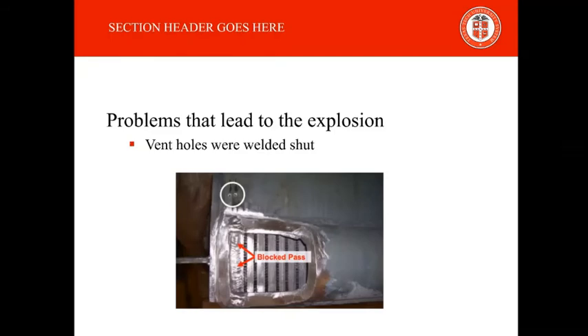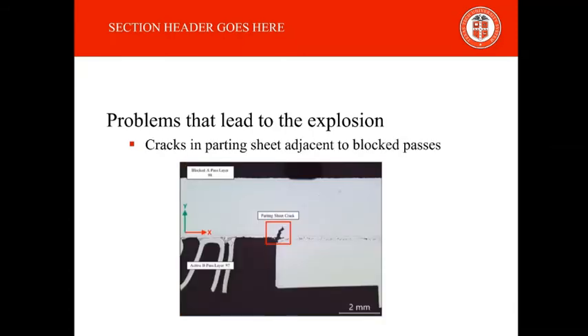The blocked ventilation holes inside the blocked layers would not have caused the problem by themselves. For a catastrophic rupture to occur, hydrocarbons must have a way to enter these layers and create the pressure inside them. The parting sheet that separates one of the blocked layers, 98, and one of the non-blocked layers showed evidence of thermal fatigue cracks and can be seen in the figure below. Assuming this crack extended through the layer, it would have allowed fluids from the active pass to the blocked off layers. This crack could have been present at the time of the 2015 repair, since no evidence is shown that they performed a leak test, or the crack could have developed in the 205 days of operation after this repair. The crack in the parting sheet adjacent to the blocked layers is the fourth and final step necessary to create the catastrophic rupture that happened on June 27th.